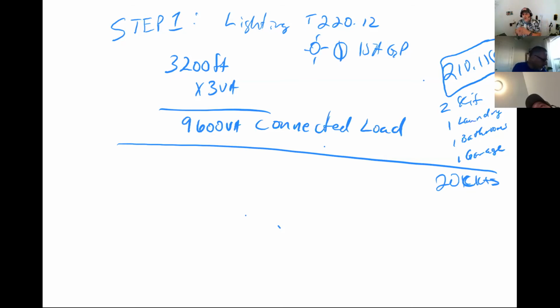Load calculation wise, when I come to size the feeders that feed the panel, each one of the 2 kitchen circuits are going to add 1500 VA according to this article to my load calculation. Right below that there's the laundry circuit, which is also 1500 VA, and right below that's the bathroom circuit.